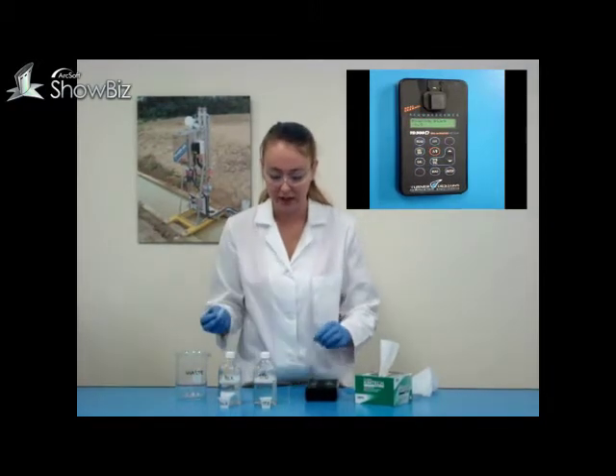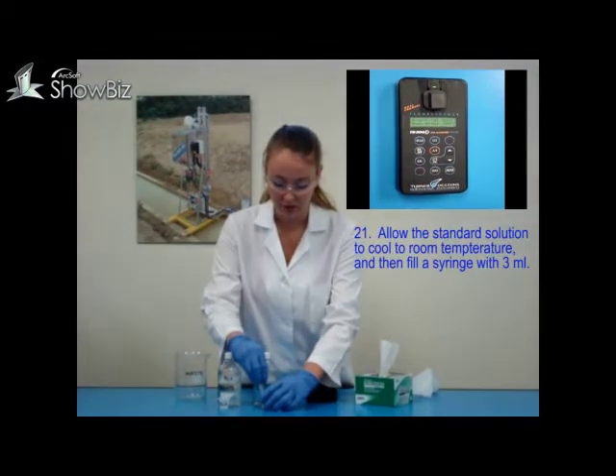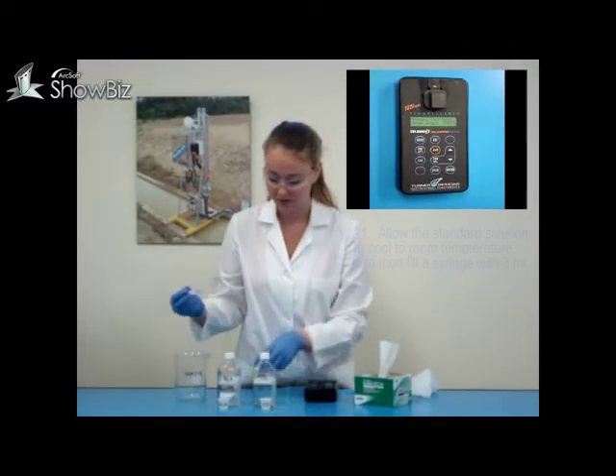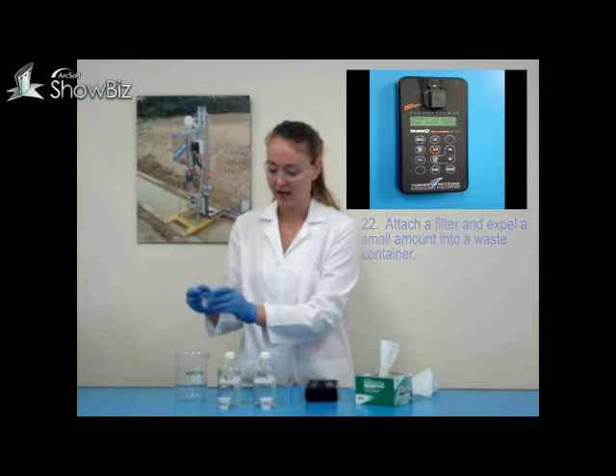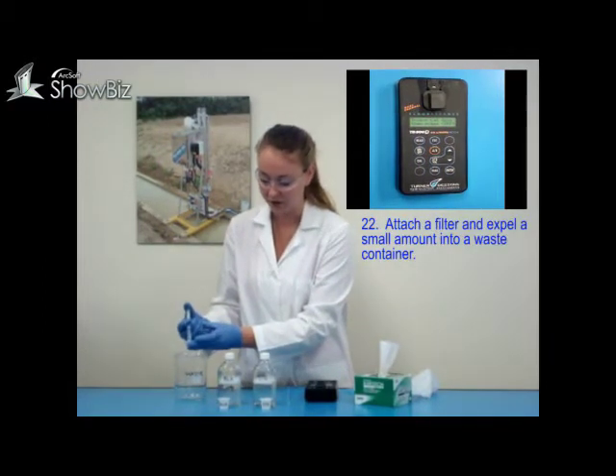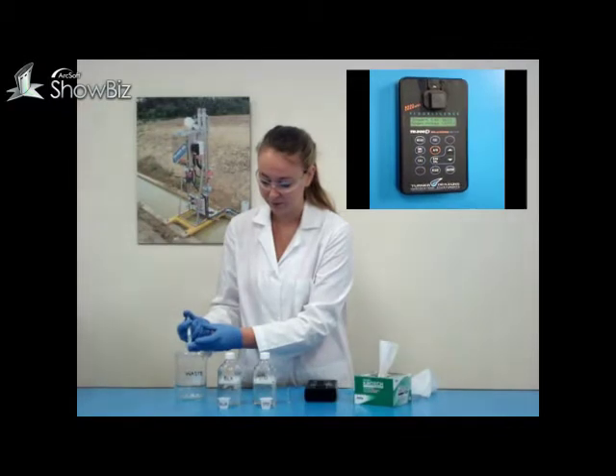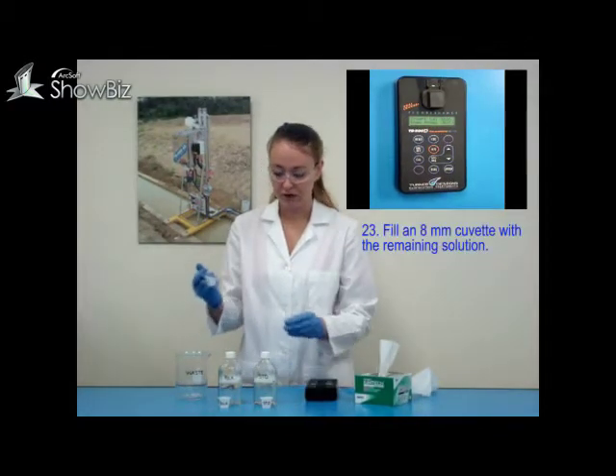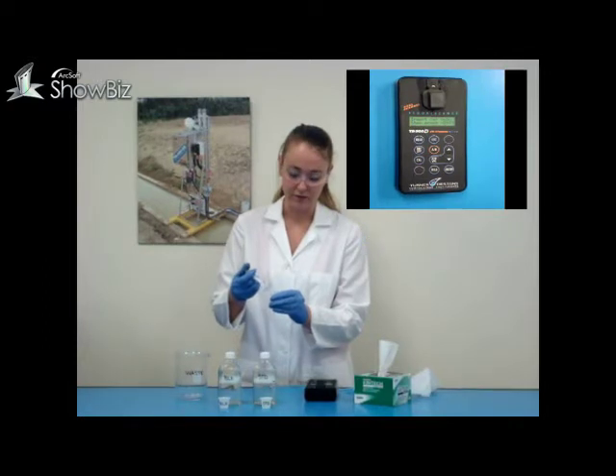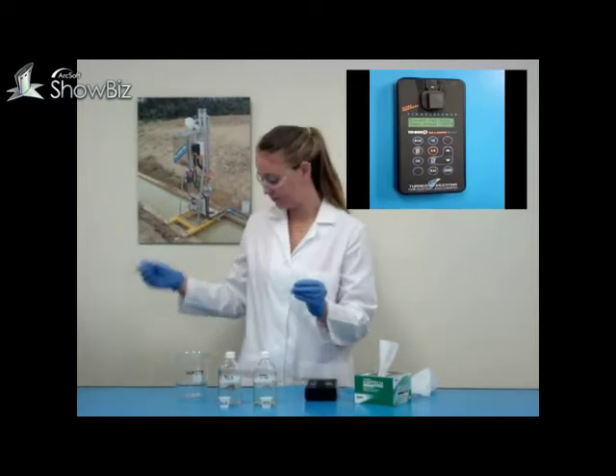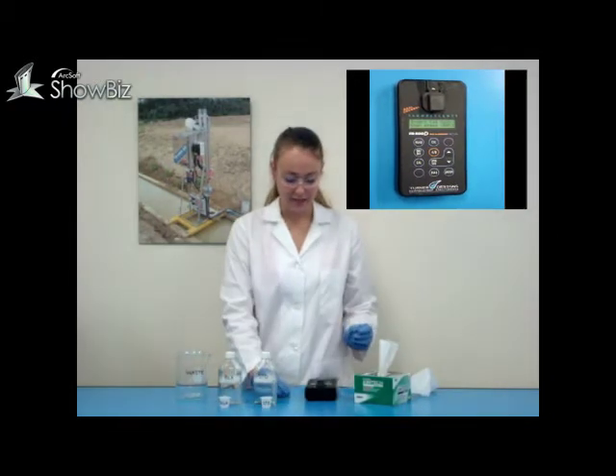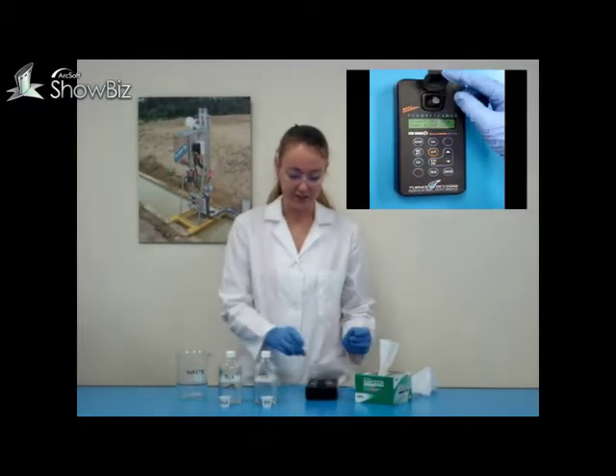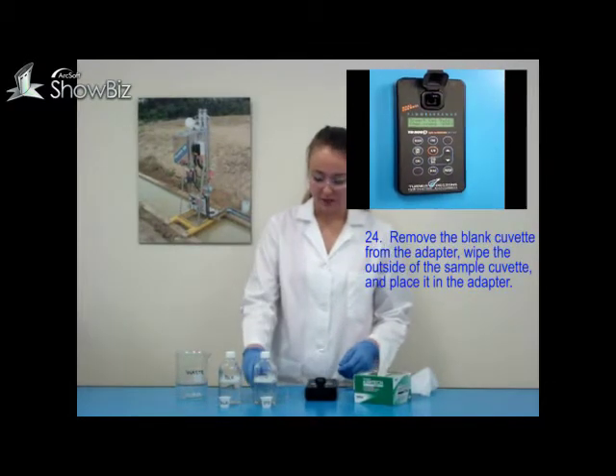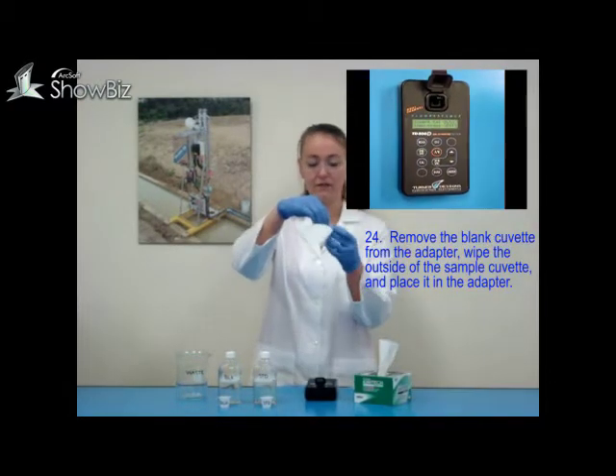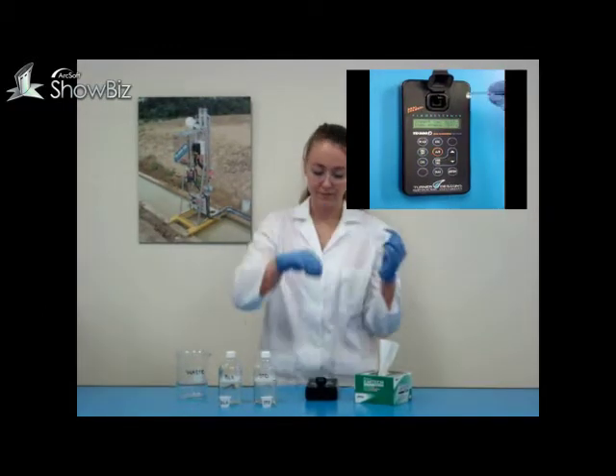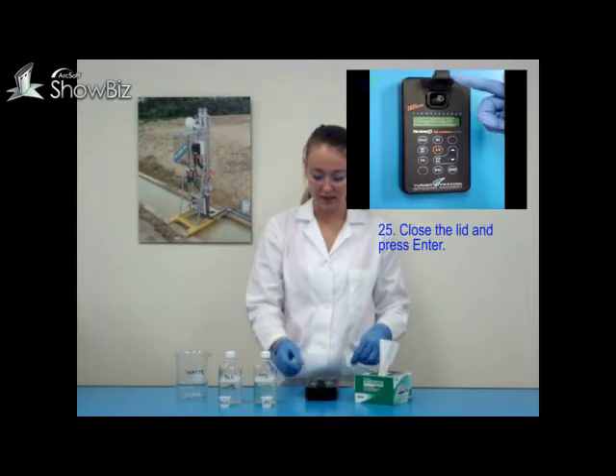Once your standard has cooled and it's clear, you can fill your syringe with 3 milliliters of standard. Attach a syringe filter, and again, waste the first milliliter or two of solution. Transfer the rest of your solution into a separate measurement cell. The TD-500D now says insert calibration solution, then press enter. Remove your blank from the instrument. Wipe the outside of your standard solution cuvette with the Kimwipe. Place into the adapter, close the lid, and press enter.